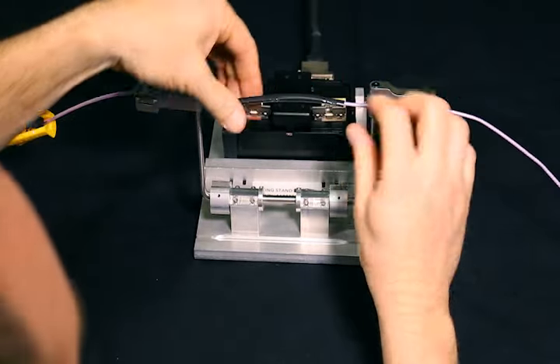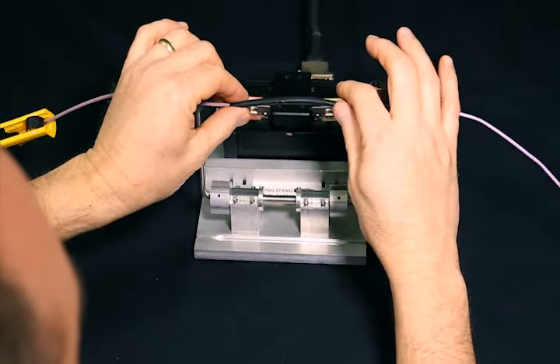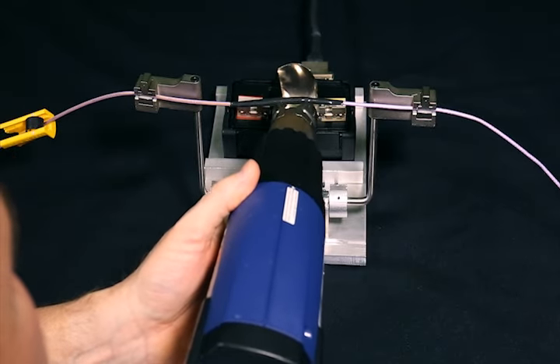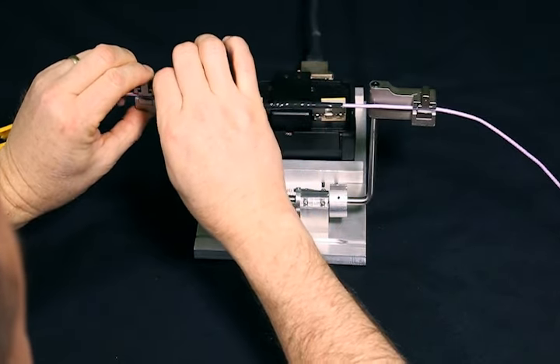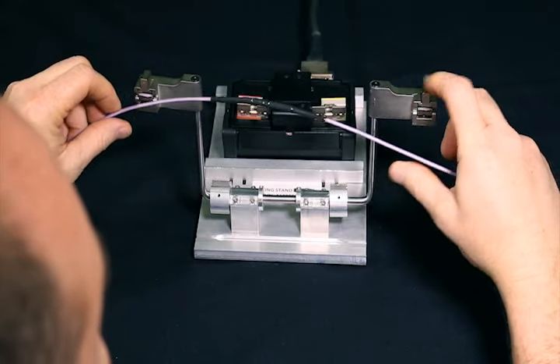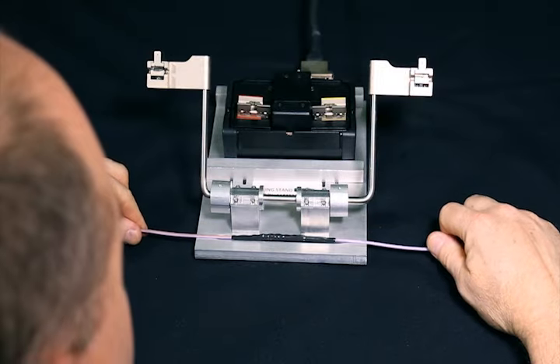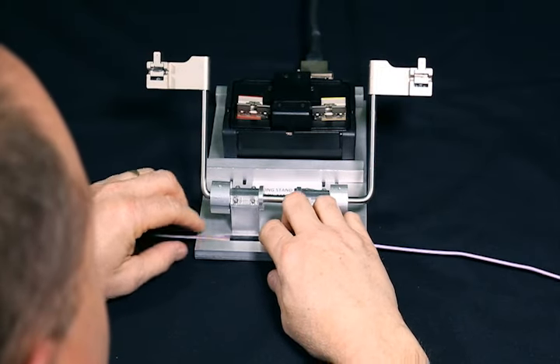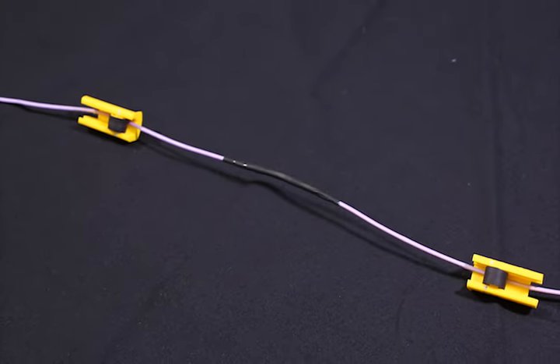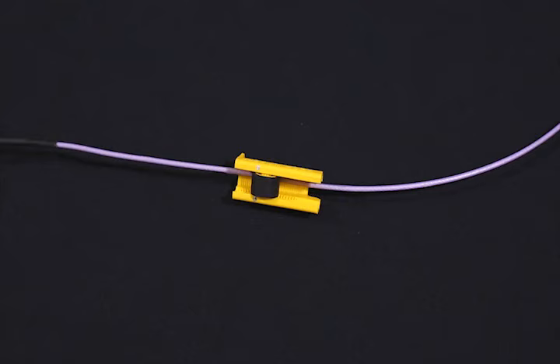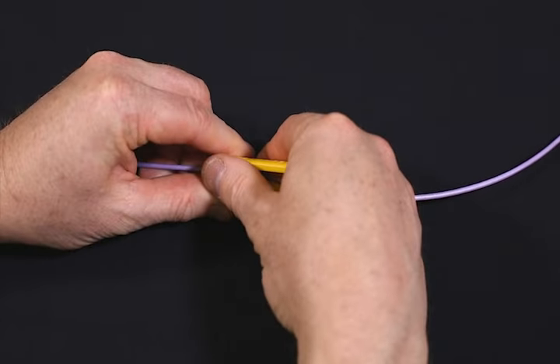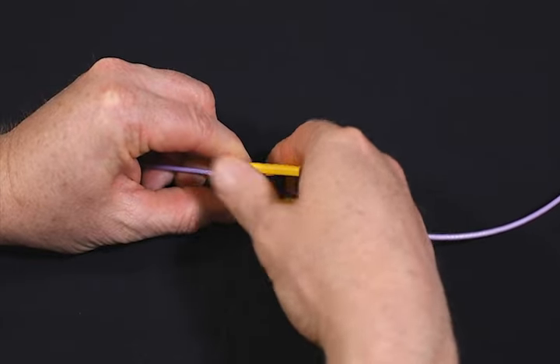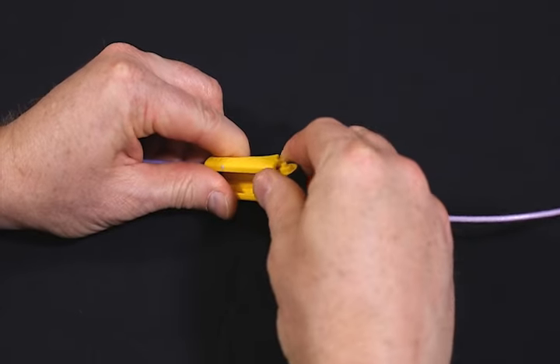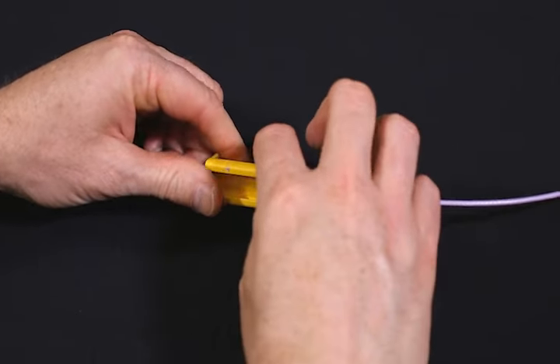Center the outer sleeve over the secondary sleeve and shrink with a heat gun. Allow it to thoroughly cool in place, or use the cooling slot in the splicing stand. Finally, remove the cable clamps from the spliced cable.